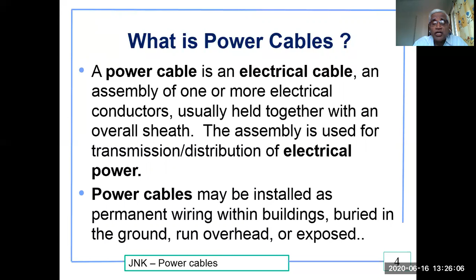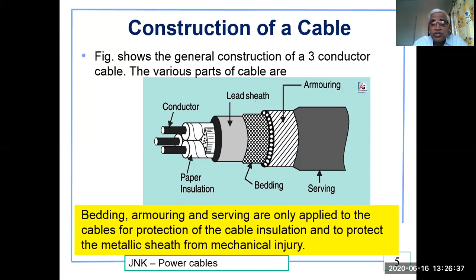Construction of a cable. The following figure shows various items in that. One is a conductor, another is a lead sheath, paper insulation between them, and there is a filling material, and there is a bedding material, and there is an armor, and there is a serving. Serving is also called outer sheath. Now, bedding, armoring, and serving are applied to the cables for protection of the cable insulation and to protect the metallic sheath from mechanical injuries.